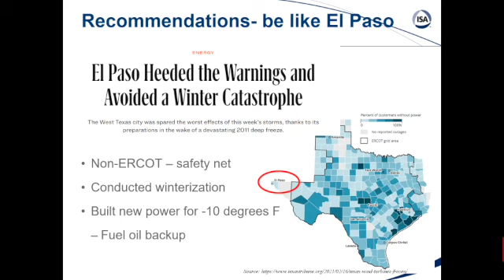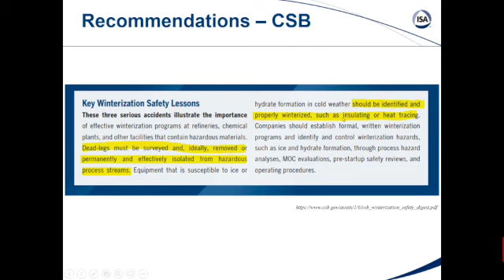If you want to dive in a little more on what's outside the power industry, the Chemical Safety Board is a great resource. On their website, they talk about, we're all in the instrumentation world, familiar with dead legs. They have horror stories of dead legs filling with condensate unintentionally because of a leaky valve, freezing, and the nasty stuff busting out and causing an accident. Their simple recommendation, and I encourage everybody to look at this: dead legs must be surveyed, removed, and effectively isolated from hazardous process streams, or winterized with insulation and heat tracing.